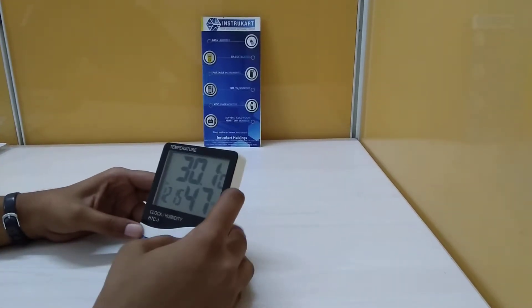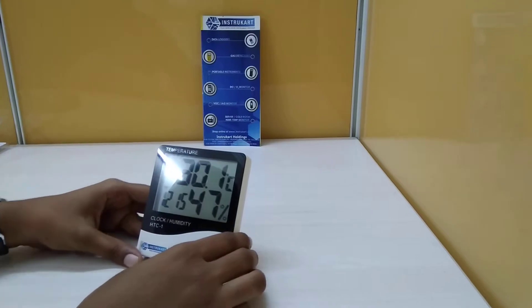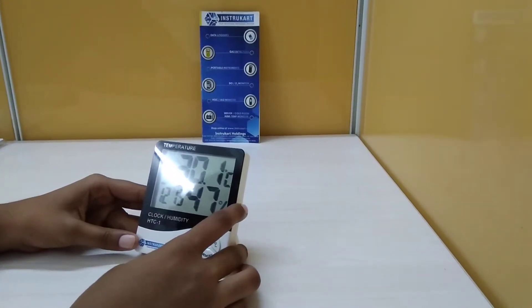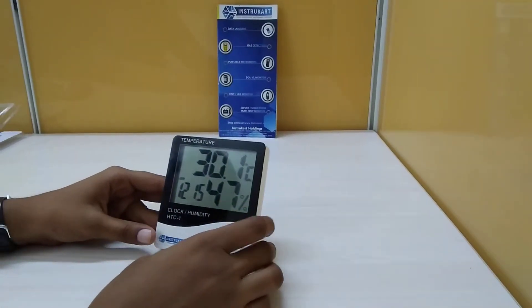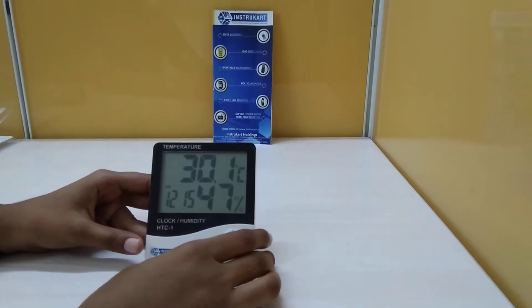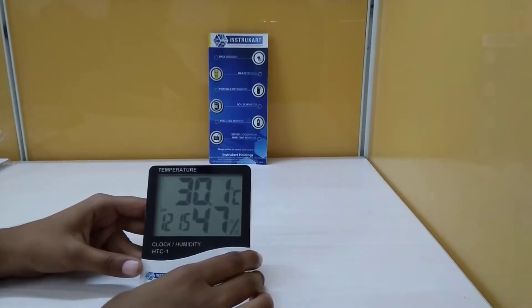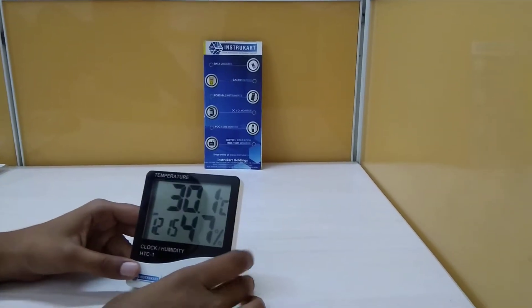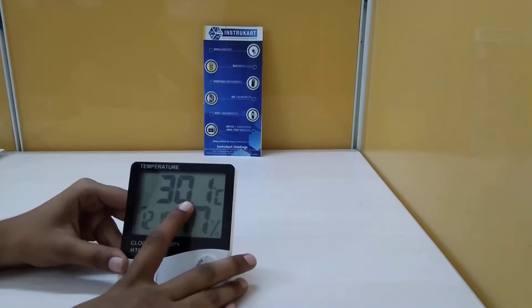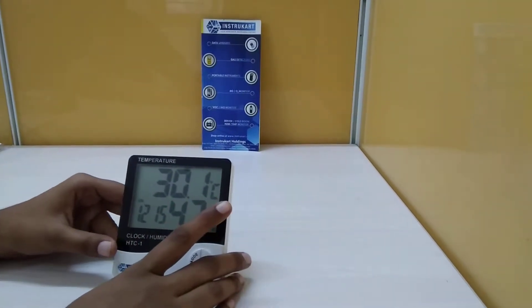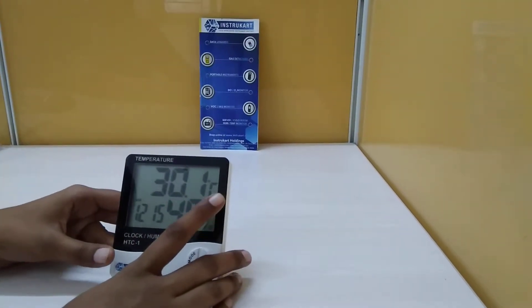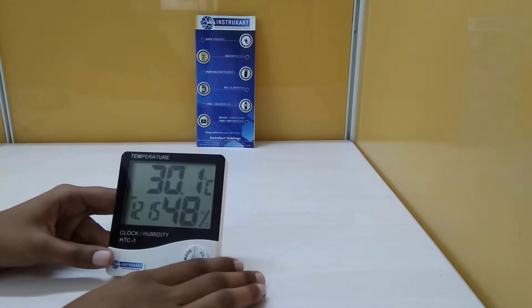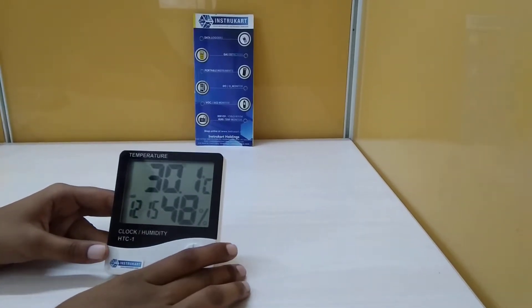It has a temperature range of -10°C to +50°C and a humidity range of 10% to 99% RH. For temperature, it has an accuracy of ±1°C, and for humidity, an accuracy of ±5% RH.